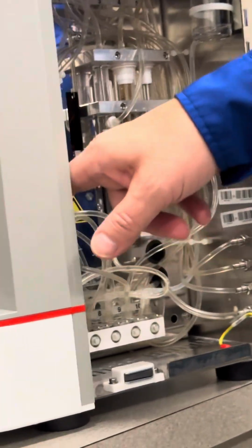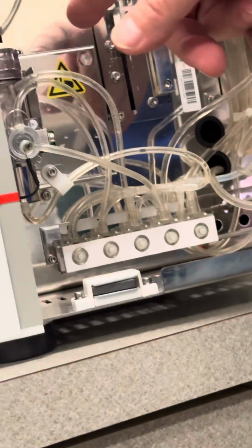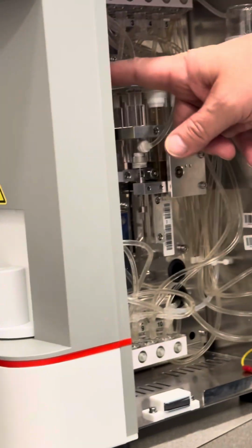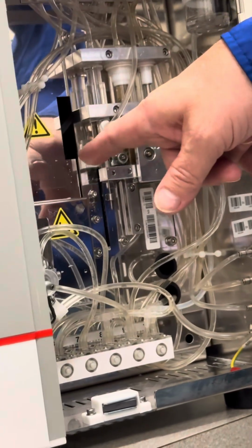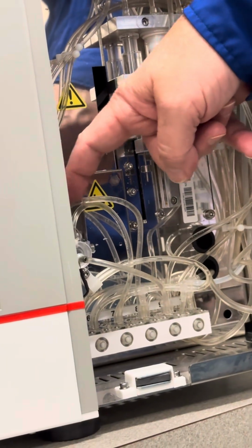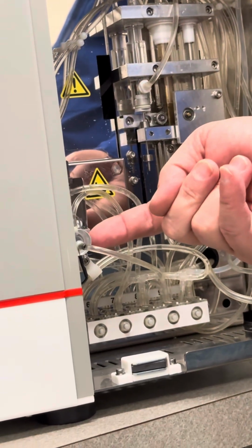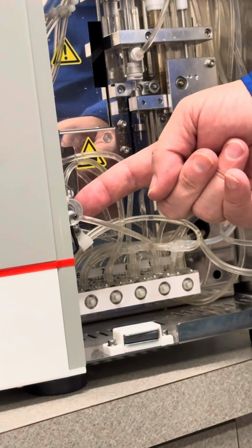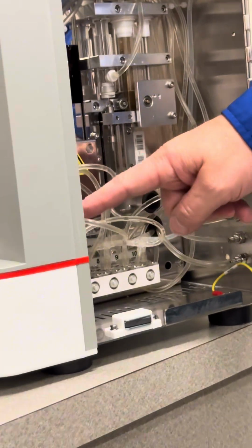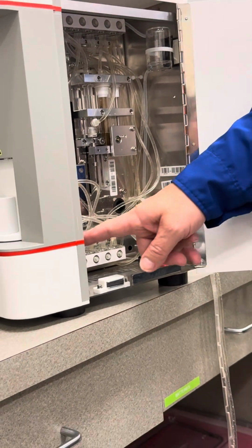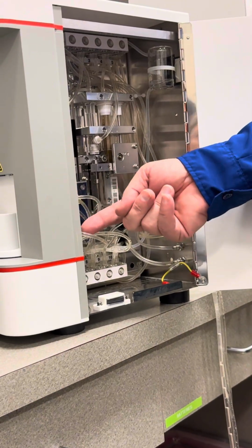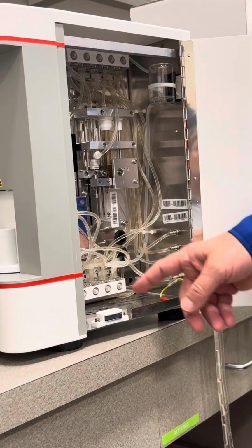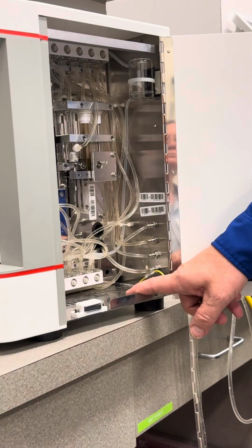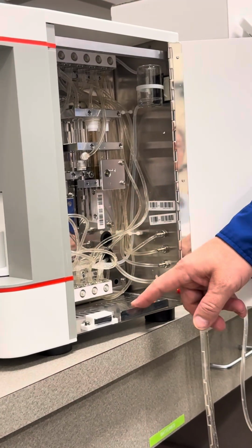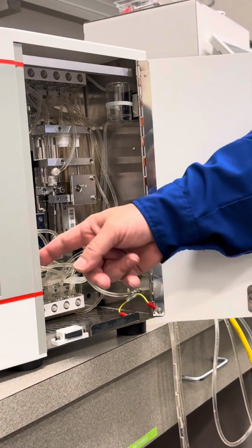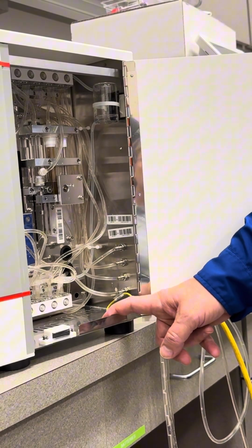This is your diluting chamber, so it does everything here, and you have the sample probe. This is your main aperture that it uses to do the counts for the white cells, the red cells, and also your hemoglobin, all done within this area here. Do you have to clean it very often? No, I did take it out the other day to clean it.